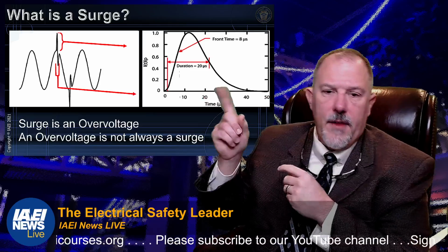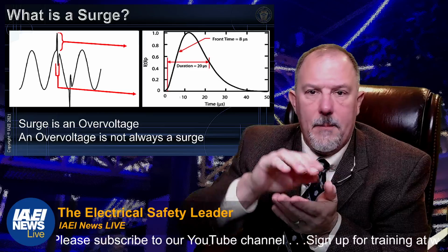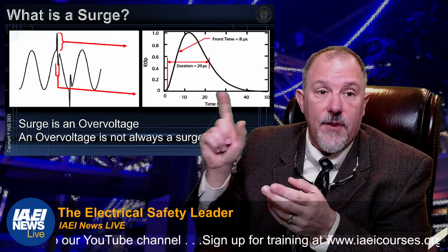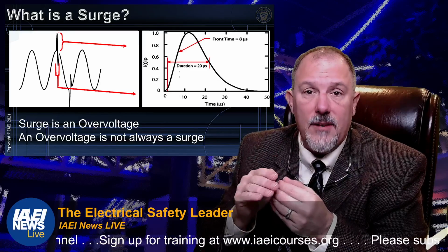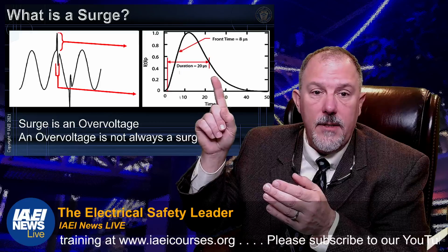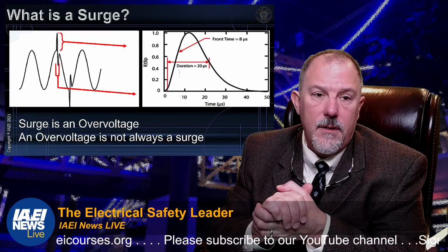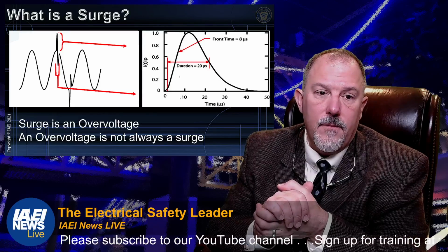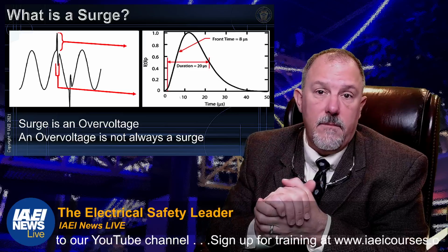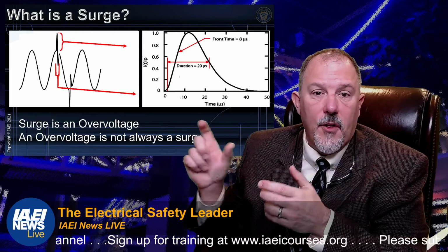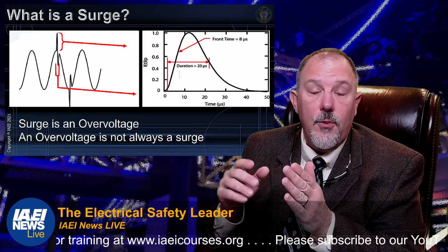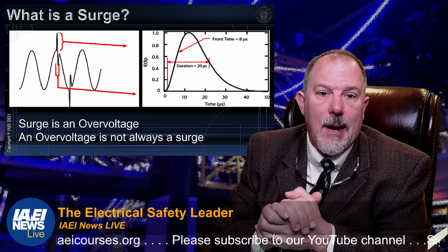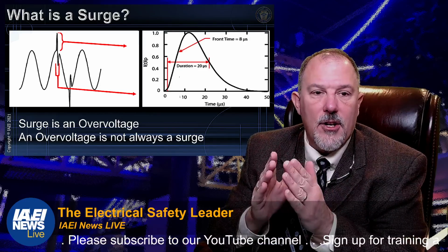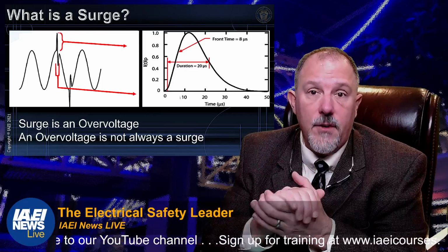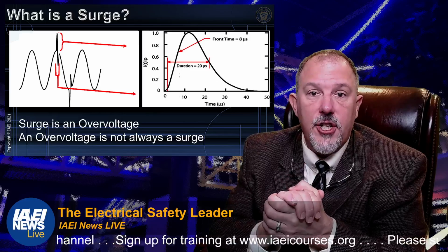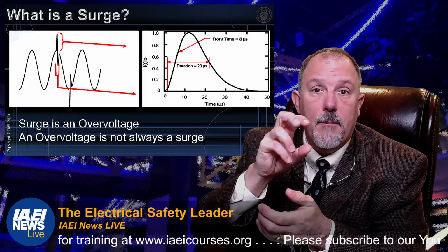Now, that image over there on the far end shows you what I meant. That's a worst case scenario, because the transient event is right at the peak of my voltage sine wave. Those are the worst case. And that's a positive one. And then the other down here is your negative transient. And that's 2 transient events in succession. Now, the duration of those is very short. You can zoom in on that one transient event up there at the top, and you'll see the microseconds that it occurs. And that very large, abrupt change in voltage will drive a very large change in current as well, because that voltage is being impressed upon a load.